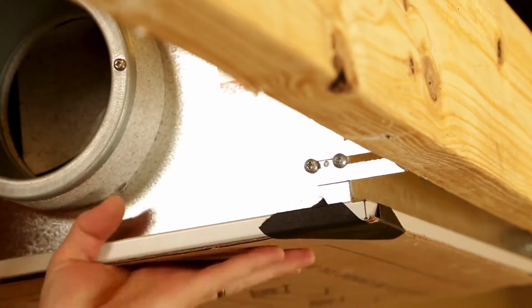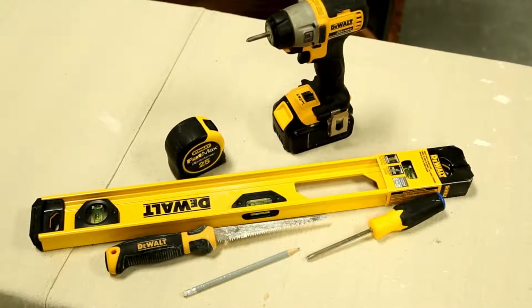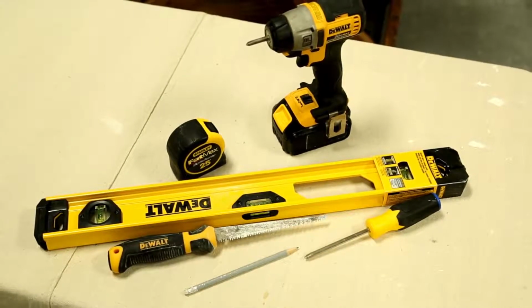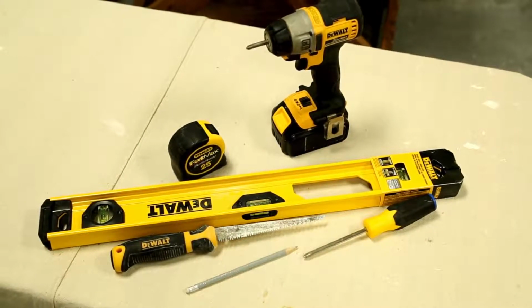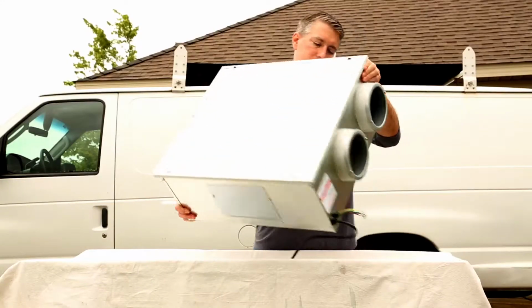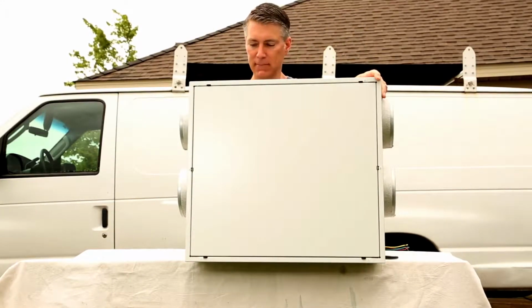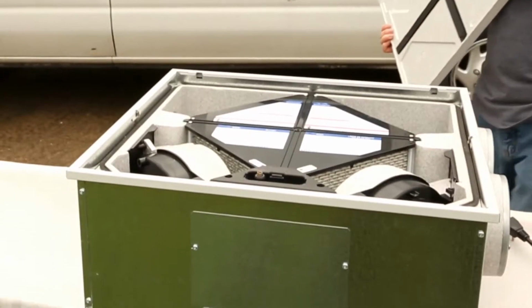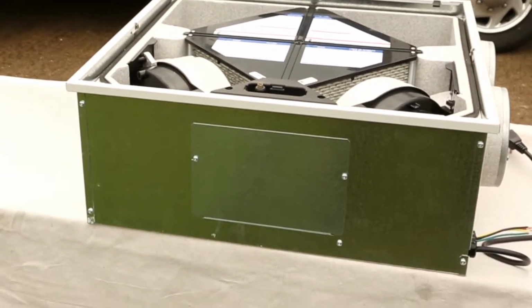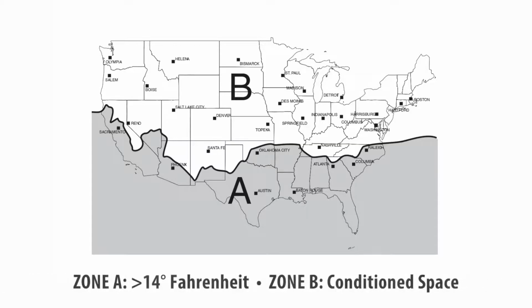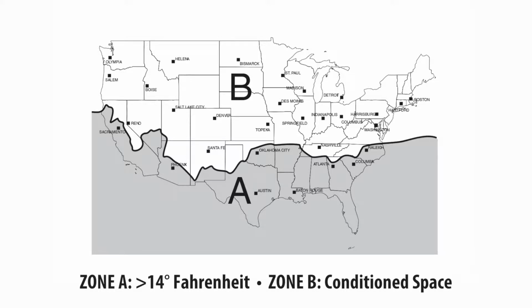All necessary brackets and screws are included with the ERVS100. You will also need a Phillips screwdriver, a pencil, a level or straight edge, and a drywall saw. The ERVS100 is designed for installation where temperature is above 14 degrees Fahrenheit throughout the year, or Zone A on this map. Units installed in Zone B must be installed in a conditioned space.